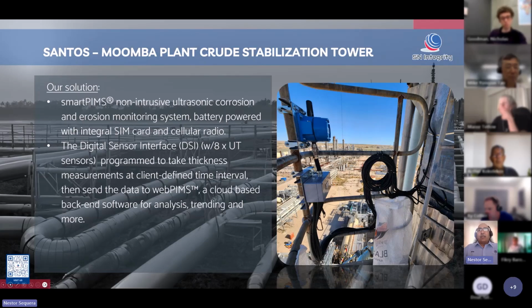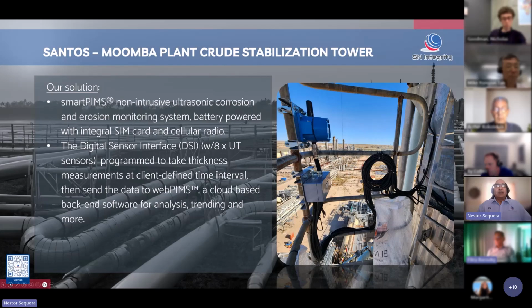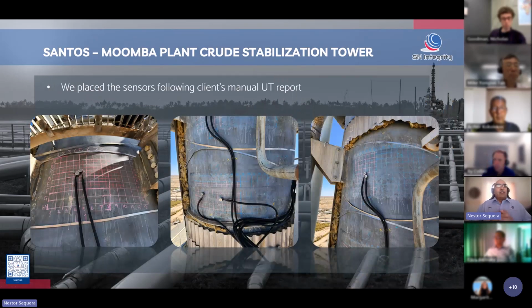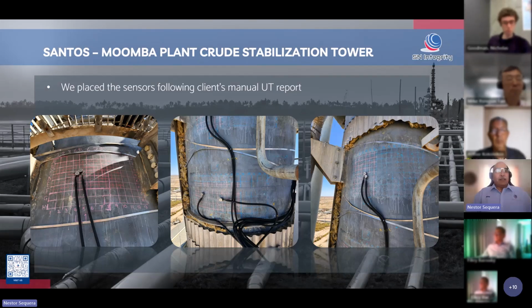The unit was set with 8 sensors. Each one can be calibrated and set individually. And there were 7 meters of cable from the unit to the location that we were monitoring. So as I said, within a week, we set everything up and traveled to site to commission this unit. For commissioning, we were guided by the maps that the team prepared. So we targeted the lowest points as shown in the figure there. We ran the sensors, as I said, each sensor individually. And we targeted 6 corroded areas, and 2 sensors were set as control points in areas where the wall is still at nominal thickness of close to 20 millimeters.